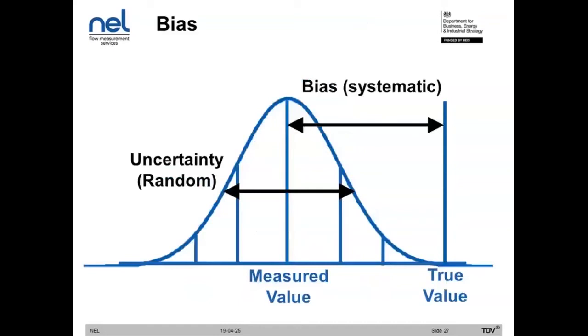We can also have bias in a measurement. I mentioned this previously when we looked at repeatability versus accuracy. What this means is you could have a device that has a fairly standard performance when it takes repeated measurements. Like maybe it measures roughly in terms of a normal distribution. So you have this spread of results where there is a cluster at the mean. However, if the device has been calibrated incorrectly and a bias was introduced at the calibration stage, then it doesn't matter what the distribution is. Your average of the measured value is still offset from the true value of the measured parameter.